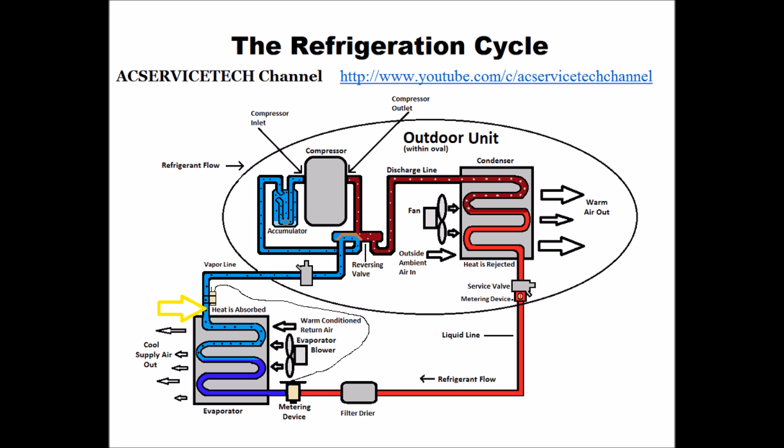In this case, since it's a heat pump, this will be considered the indoor coil — but since we're in cooling mode, that is the evaporator coil. Right where it comes out of the saturated state it turns into a complete vapor, and it increases in temperature by absorbing heat from the house until it comes out of the evaporator coil. That temperature increase in vapor form is called the superheat. The temperature increase from where it becomes a complete vapor all the way over to the service valve is called the total superheat.